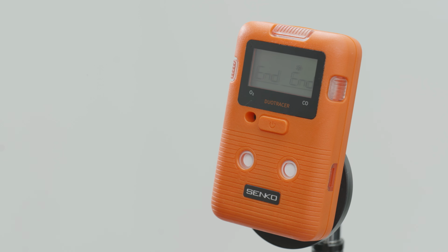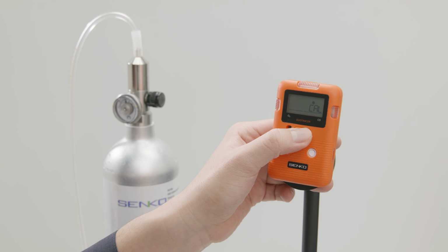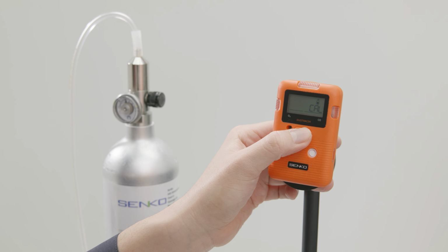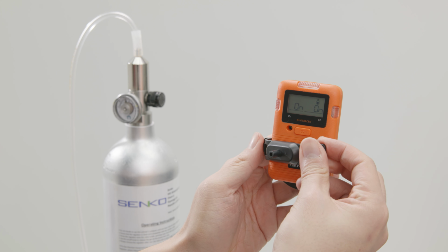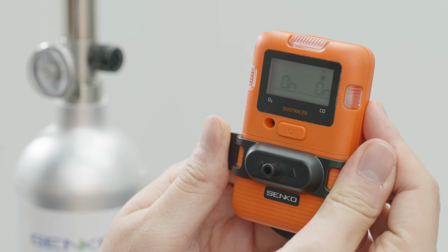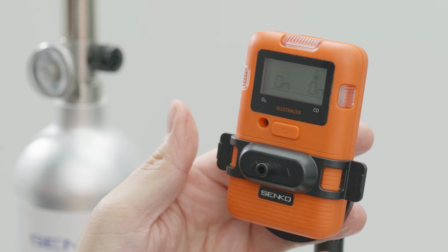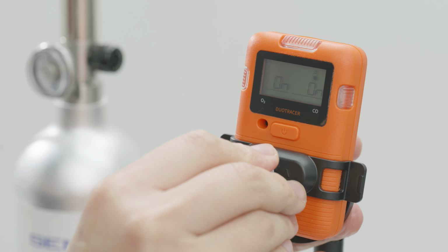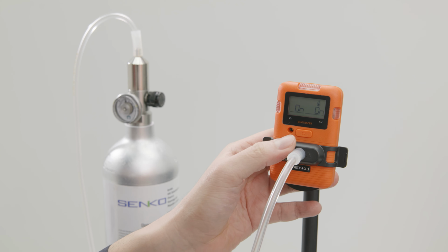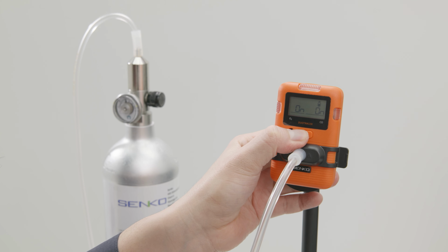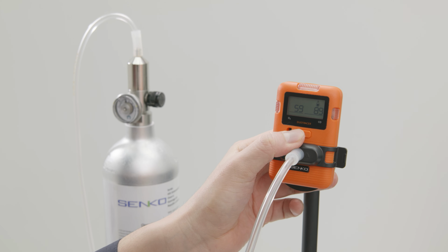Now, let's move on to span calibration. First, look for the cylinder icon on the screen, which indicates span mode. Just like with zero calibration, start by selecting the gas channel you want to calibrate. Then press and hold the button again, and the span calibration countdown will start automatically. At the same time, connect the Duo Tracer calibration cap and air hose to the standard calibration gas cylinder and regulator for the target gas, and begin supplying the gas. During the countdown, Duo Tracer automatically adjusts the sensor response based on the input from the standard gas.